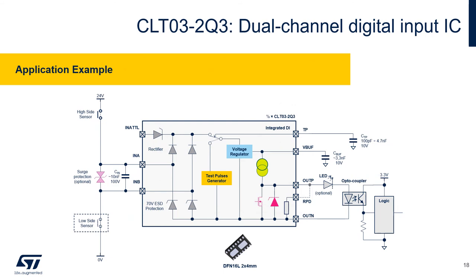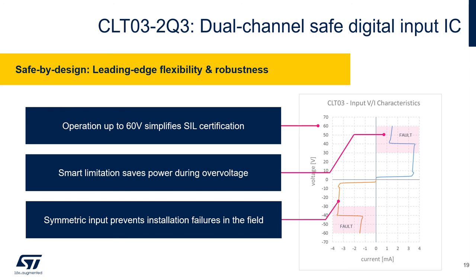This is the typical application diagram showing connection of high side or low side sensors. There is also an optional transil diode for surge protection if it is required, and a very few external capacitors. The output drives an optocoupler in this case, but it also enables multiplying the amount of optocouplers or even making a combination with a status LED. The 60 volt tolerance improves reliability and simplifies achieving safety integrity level certification. When the voltage at the input exceeds operating conditions above approximately 30 volt, the input current is limited to even much smaller values — a smart way for further reduction of power dissipation at overvoltage conditions.